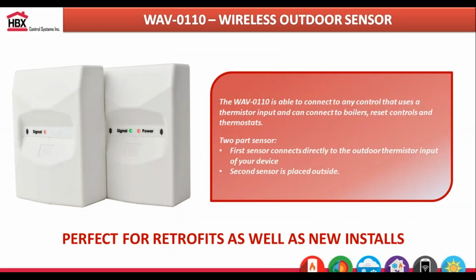In terms of the outdoor sensing, we want to have outdoor sensing with our snow melt controllers because obviously we don't want them to turn on in the summer months. So we'll go into warm weather and cold weather shutdown through the use of that outdoor sensor. We do also offer a wireless outdoor option as well.